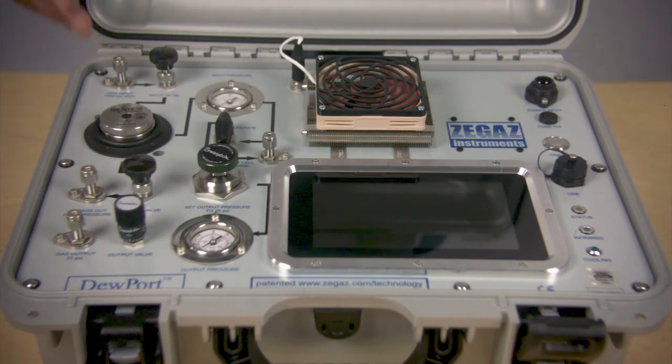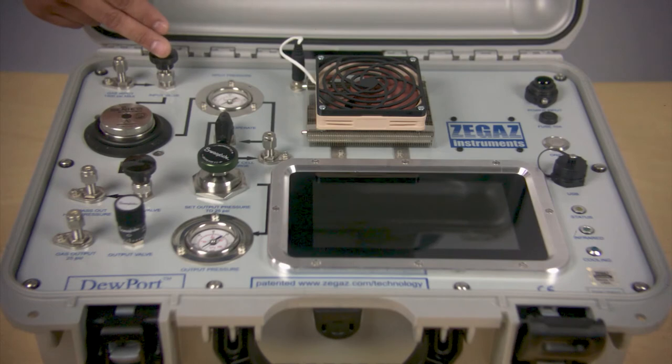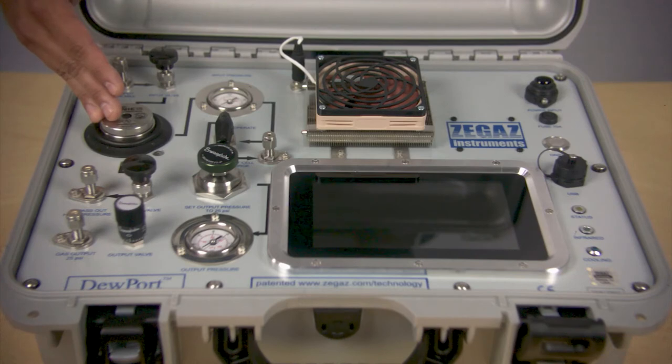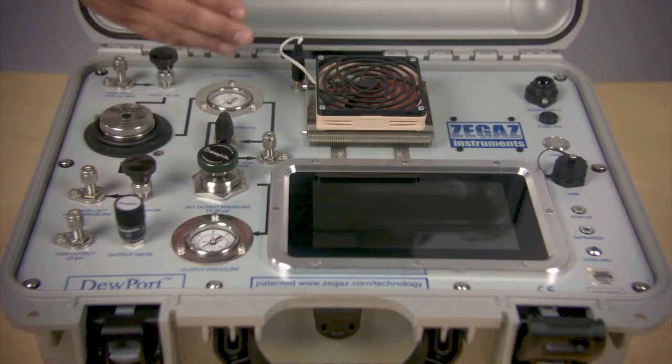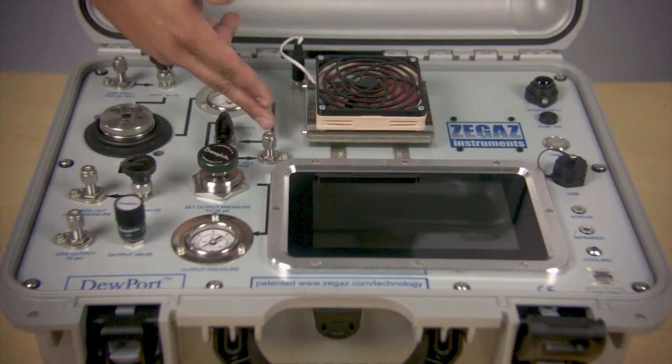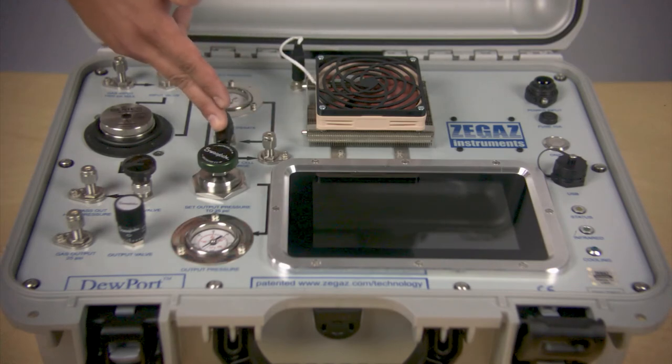We have our gas input port and valve to introduce gas into the unit. The sample will pass through a liquid block membrane filter and pressure will be indicated on the input pressure gauge. It will then flow into the analytical cell which has a purge function controlled by the operate purge valve. We will go into more detail on this feature in the maintenance section.